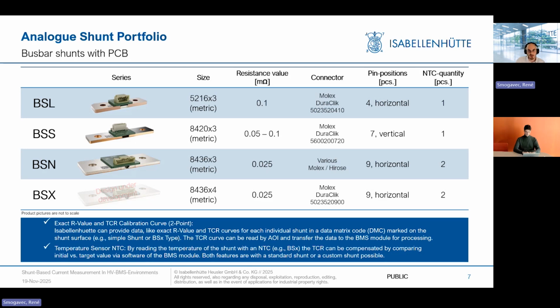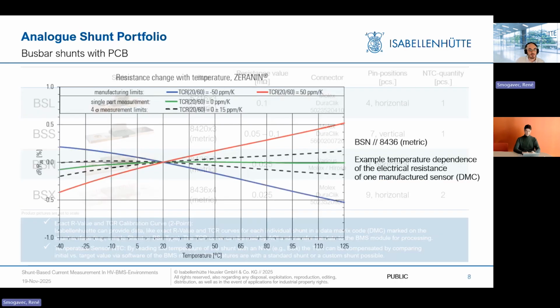For a functional safety reason, we use redundant measurement points that are a bit dependent on connector pin count. For the BSL, we only have 2 measurement points. For the other ones, we have more. And for this analog shunt series, we also have 1 to 2 NTCs, thermistors, and the TCR equations and curves also saved in the DMC to gain a platform for TCR compensation, making the TCR curve way flatter.